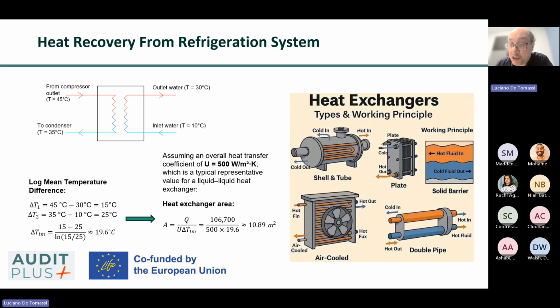Heat recovery from refrigeration systems can be implemented using several types of heat exchangers selected based on temperature levels, fouling risk, pressure constraints, and whether the recovered heat is transferred to water, air, or another process fluid. Shell and tube heat exchangers are commonly used in industrial refrigeration heat recovery, where robustness and tolerance to higher pressure or fouling are important. They consist of refrigerant flowing through tubes, while the secondary fluid, typically water, flows around them in a shell. They are suitable for medium to large systems and can handle relatively high heat duties, but they are less compact and generally less thermally efficient than plate designs.